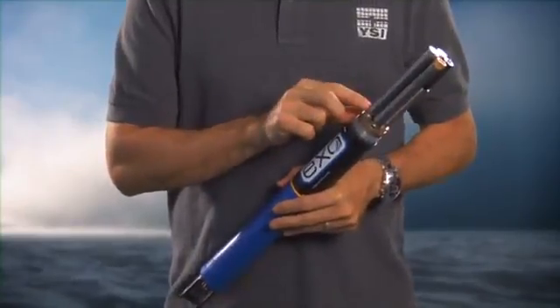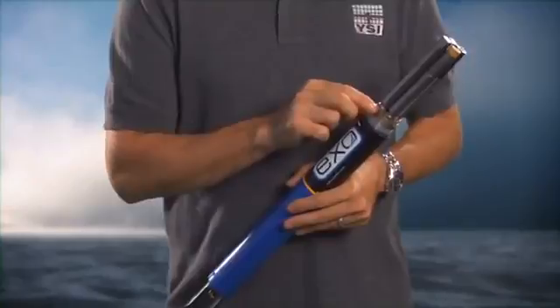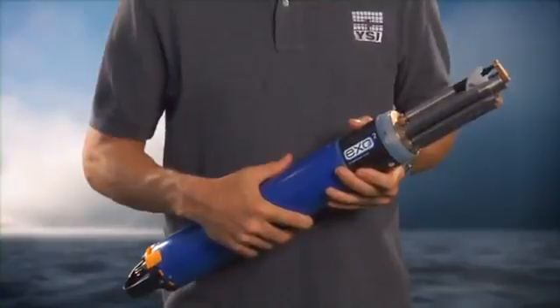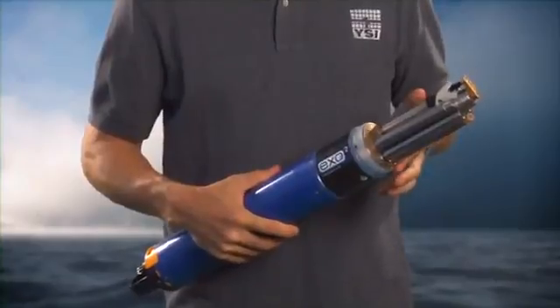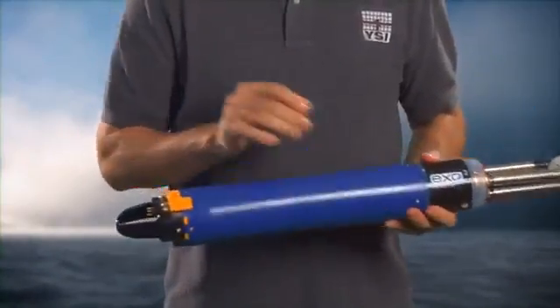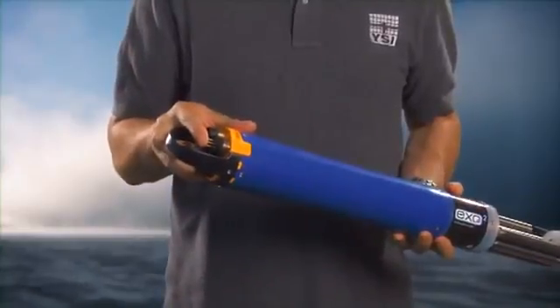The sondes are the controllers for the sensors and supply power and data logging functions. The Exo-1 sonde has four sensor ports and is only 1.85 inches in diameter and 25 inches in length. The Exo-2 has six sensor ports, an anti-fouling wiper port, and an auxiliary port to daisy-chain additional sondes or to integrate third-party sensors. The Exo-2 has a 3-inch diameter and is 28 inches in length.